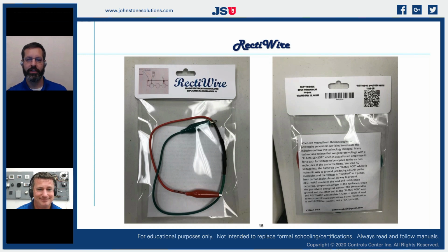I had another thought too, just on the service side of it. If you guys are ever coming across a building that's got lots of flame rectification issues, and you're going in there and cleaning that flame sensor, often anything that's going to insulate that flame rod is going to stop this flow of electrons. So I have found on quite a few times that on single pipe systems and furnaces where it's bringing the combustion air in from the mechanical room, a lot of times any kind of chemicals or dust or anything, your salt bags for your water softener, any kind of chemicals that are brought into the combustion process through the intake will coat that flame sensor, and you'll have environmental issues that are causing you to clean that flame rod more often than you should. So be aware of the environment around what's being brought into the combustion process too, because it actually will bake those chemicals onto that flame rod.